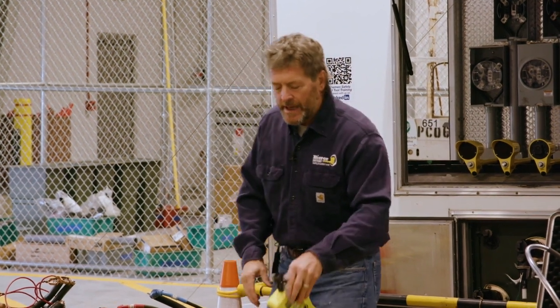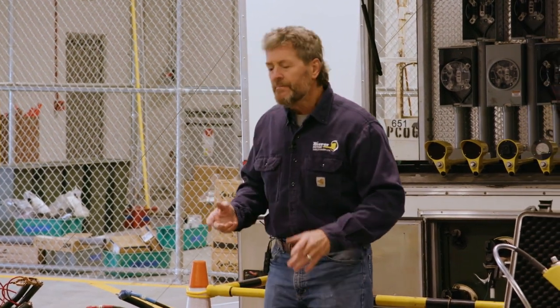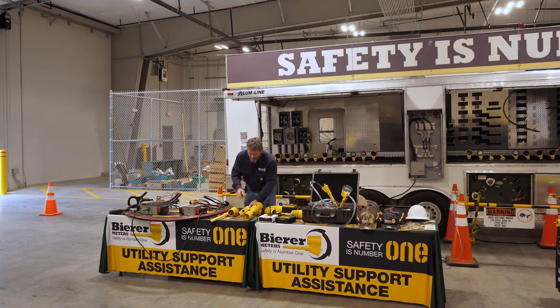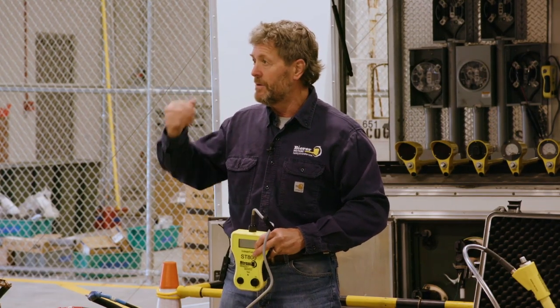What you do is pull the meter, go to the lugs of that meter or the meter jaws. The secondary is energized, so you go hot leg one to neutral. Turn the tool on and look at your voltage. In this particular case, we're seeing about 100 volts, so obviously one of those legs, hot leg one or neutral, is bad. The tool's already telling you that.